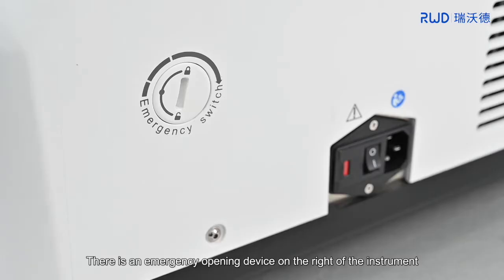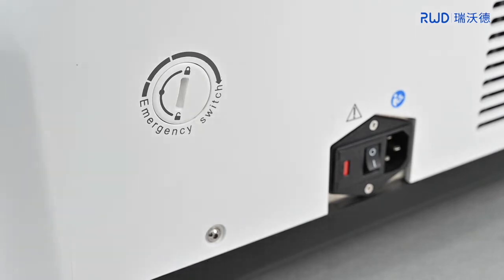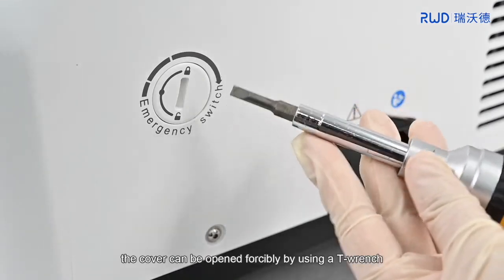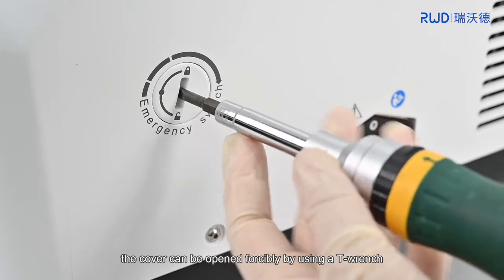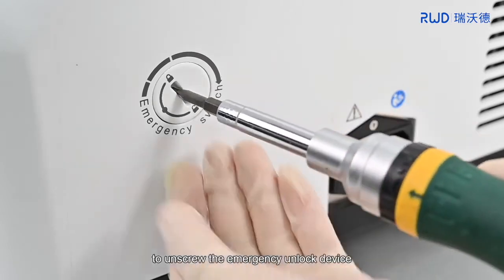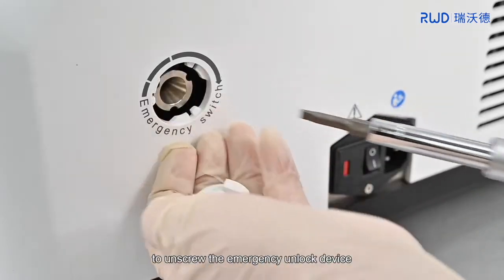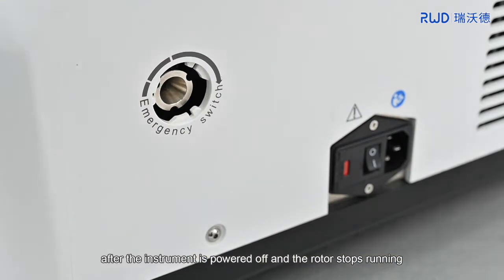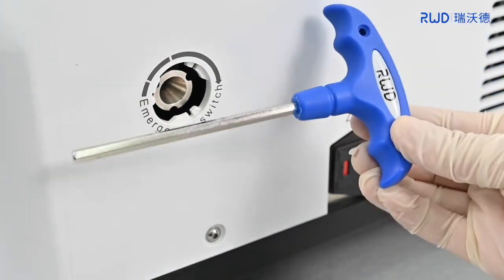There is an emergency opening device on the right of the instrument. When the centrifuge cannot be opened manually for various reasons, the cover can be opened forcibly by using a T-wrench. Unscrew the emergency unlock device after the instrument is powered off and the rotor stops running.